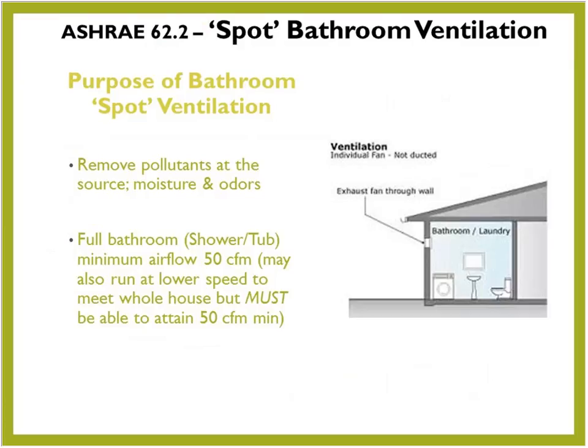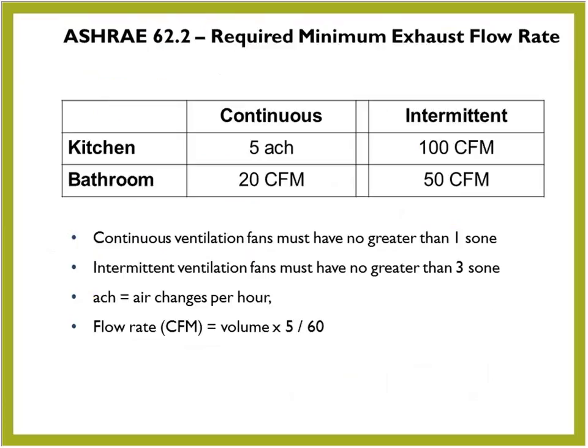Okay. So spot ventilation, which I would require, or I would recommend in any event, getting the moisture from the shower and the odors from the kitchen out right at their source is the ideal situation. No matter what ventilation system you're using, I would recommend spot ventilation. Most of the codes will require that the bathroom fans be tested at an efficacy of 50 CFM, and if there's a range hood fan or a fan in the kitchen anywhere, it needs to be able to achieve 100 CFM intermittently.